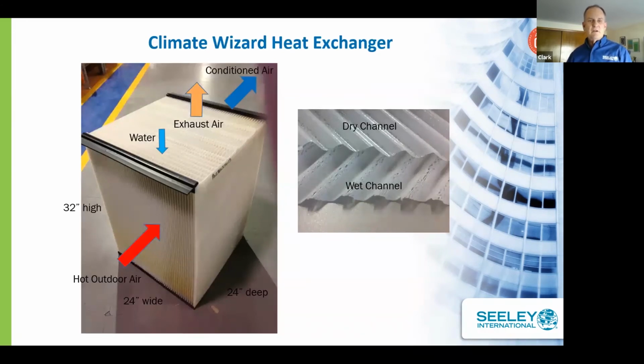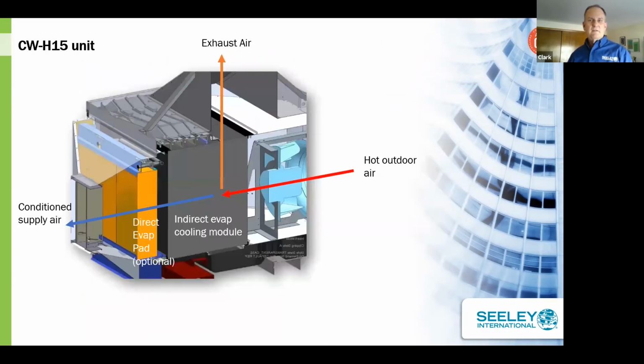Here's a picture of our heat exchanger core, and you can see the hot air comes in through the face of the heat exchanger. We put water in at the top, and then we have conditioned air coming out the back side. There are some dimensions. It's roughly 24 inches deep, 24 inches wide, and 32 inches high. And then the exhaust air comes out the top. So this will cool below the wet bulb temperature.